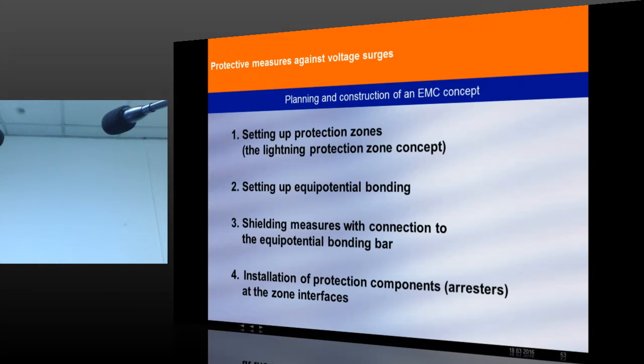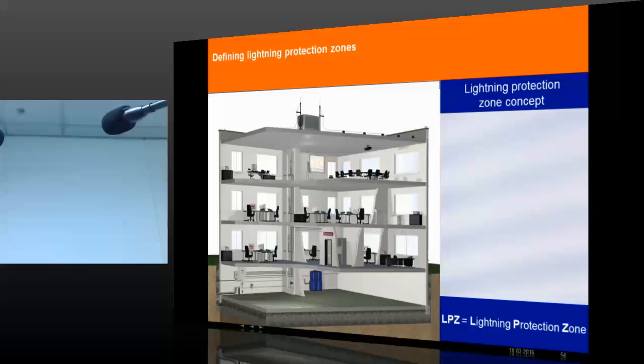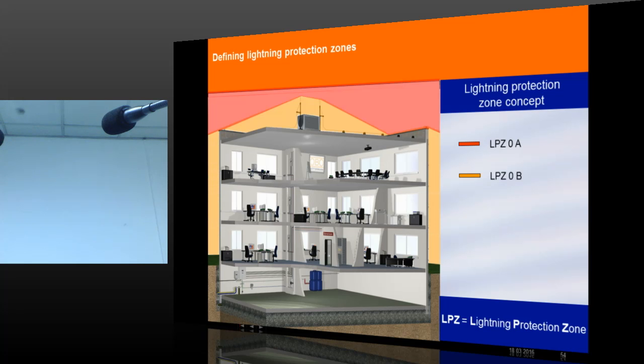So, when we talk about the internal lightning protection system, what is important for you is setting up a protection zone: lightning protection zones in a building, setting up equipotential bonding, shielding measures, and installation of protection components. These are the 4 subjects which need to be considered. What is a lightning protection zone? A building to be protected is divided into various LPZ. LPZ 0, LPZ 0A, LPZ 0B, then LPZ 1, LPZ 2 and LPZ 3.